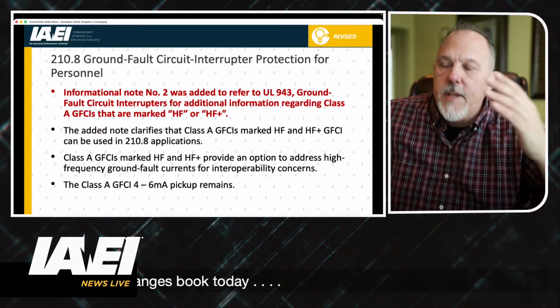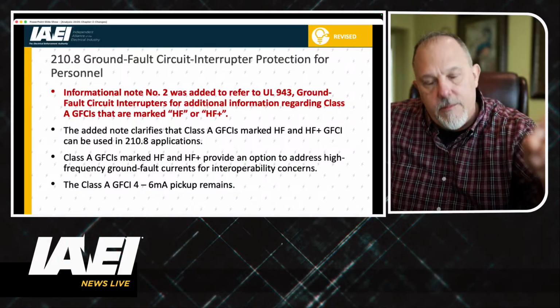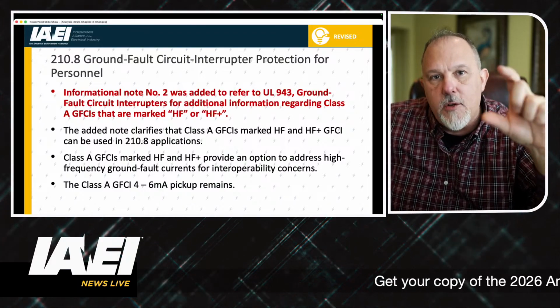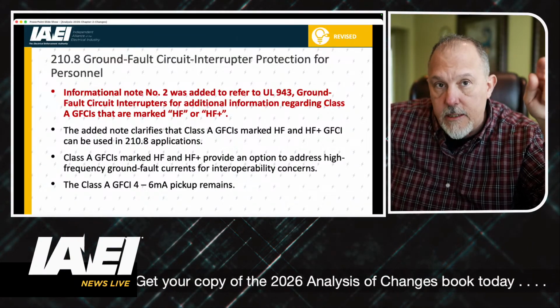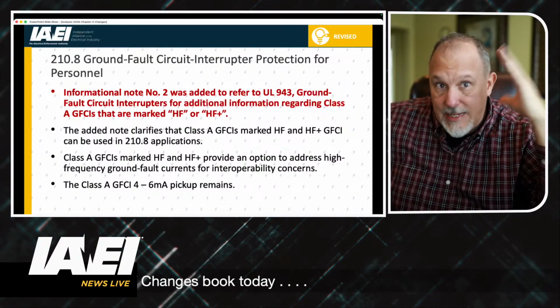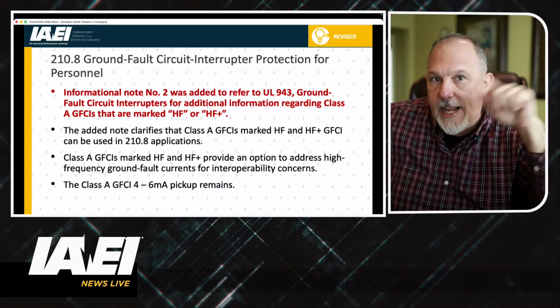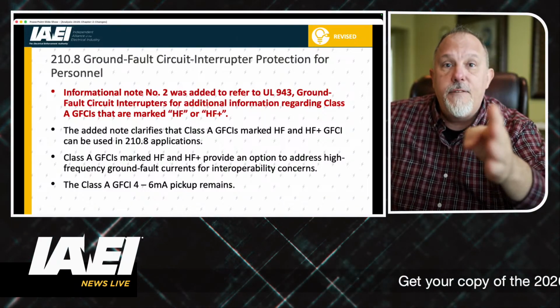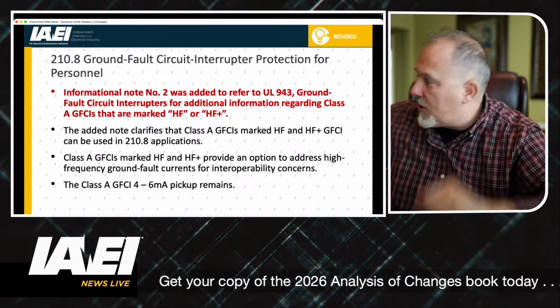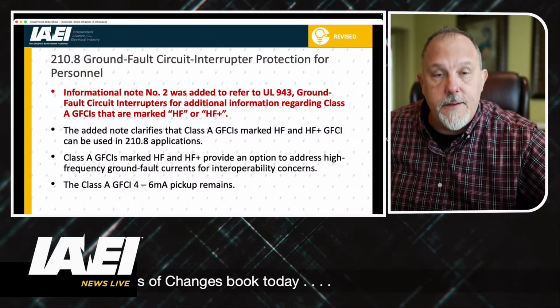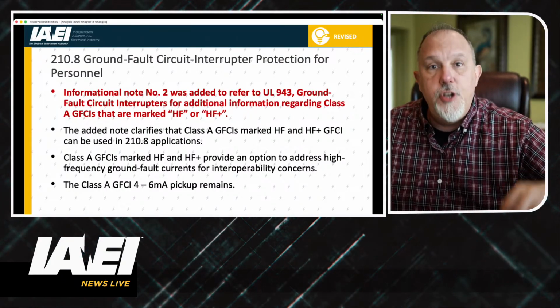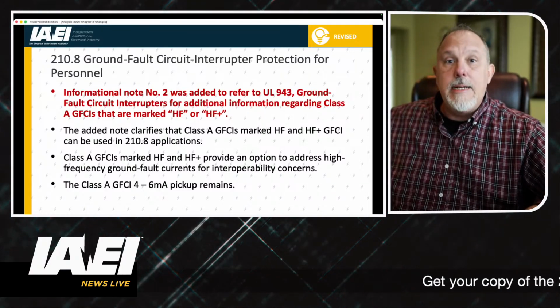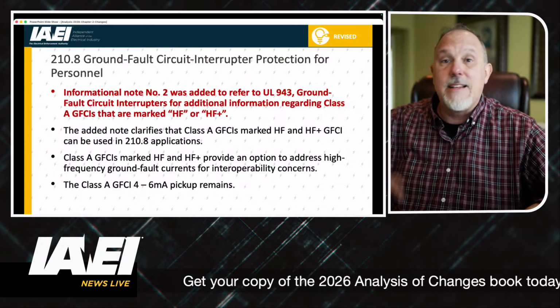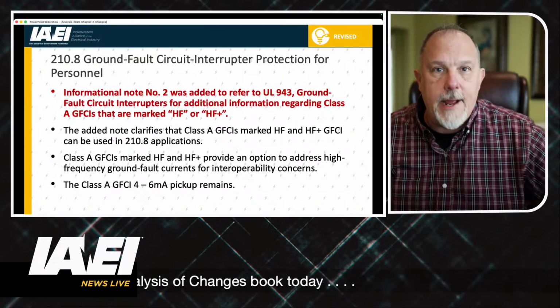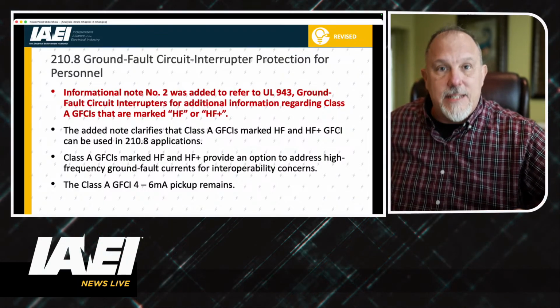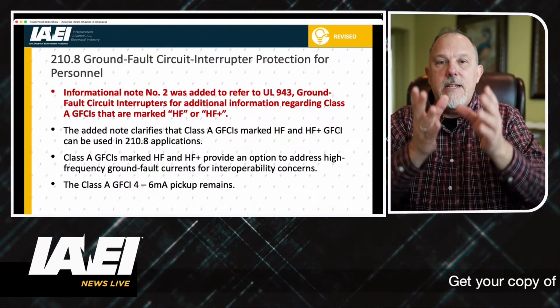So the HF version of the GFCI, I won't say version, what would I call it? It's a type. It's very similar to having a receptacle that has a TR or a WR, weather resistant or tamper resistant. It's still a receptacle. A GFCI marked HF is still a GFCI. If I put a receptacle in this room that had a WR on it, I would not be violating the National Electrical Code. I don't need a weather-resistant receptacle in this room. But the fact that it's labeled WR doesn't mean I'm violating the code, because the requirement is that I need a receptacle. So the fundamental rule is it is a receptacle.